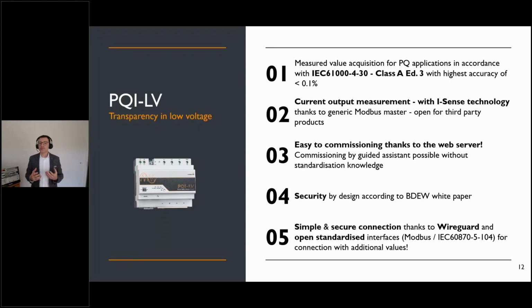You can measure not directly with these measurement inputs on the device, but with external equipment, with our iSense technology, also currents of the feeder, thanks to a generic Modbus master. We are also open for different third-party products. My thinking is that if you install a product and you have different other feeder measurement technologies installed, the product at the transformer station must also be able to record these third-party products and transfer them in other protocols like 61850 or 104.